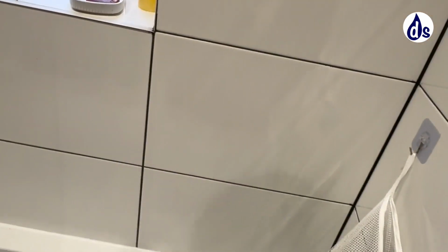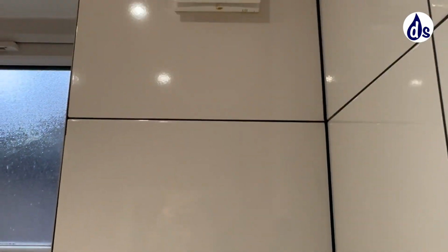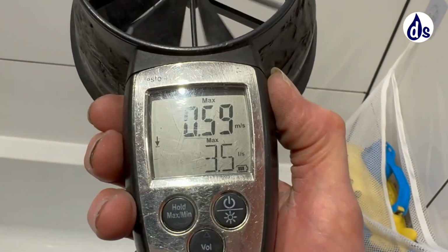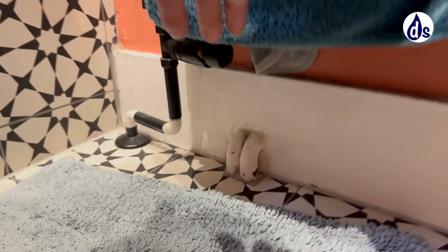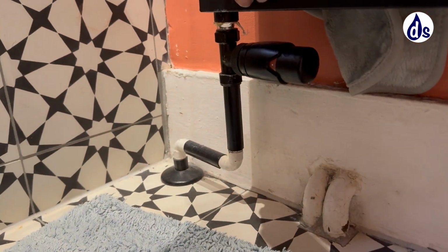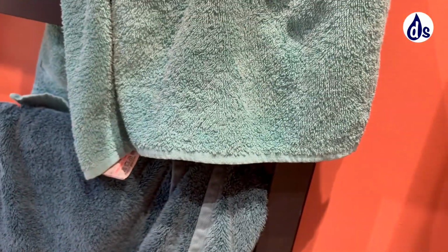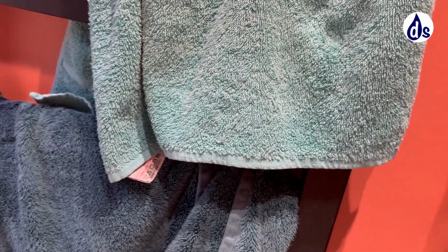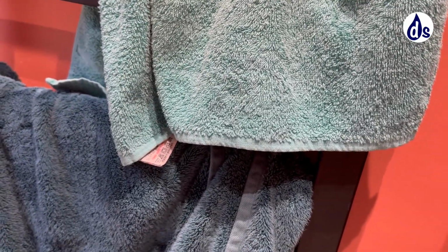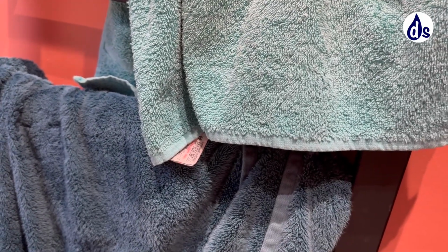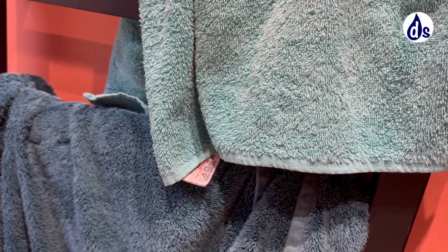The other thing is that I can't test it when the top is on, so I'll take it off. But again, I don't find a huge difference. Yeah, so it's saying 3.5 litres, and it should be 15. It's that second number. In terms of stopping mould and condensation in the rest of the property, it's actually better to have slightly lower temperature in the bathroom and the air flowing through it, and then drawing the heat from the rest of the house, rather than wasting air coming out of the bathroom. So just keep the light on and the door closed. I mean, these things don't consume much heat, so electricity, energy even.